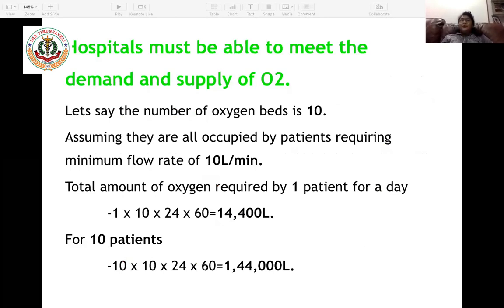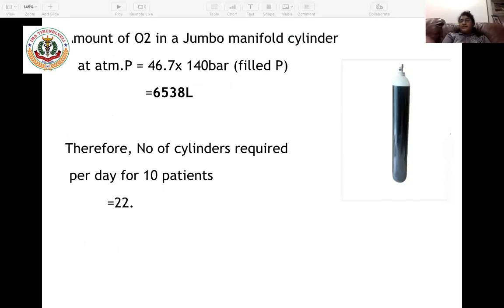Hospitals must be able to meet the demand and supply of oxygen. Let's say the number of oxygen beds is 10. Assuming that they are occupied, those 10 patients need 10 liters per minute each. One patient at 10 liters per minute for 24 hours times 60 minutes, the total need is 14,400 liters. For 10 patients, that increases to 1,44,000 liters. The amount of oxygen in a jumbo manifold cylinder is 6,538 liters. So for 10 patients, you need to have 22 cylinders at a time.